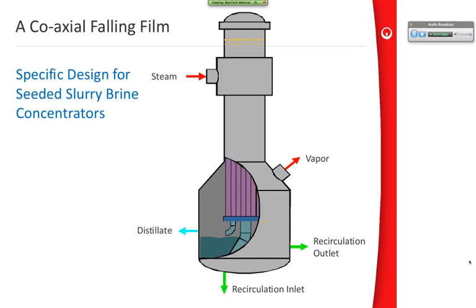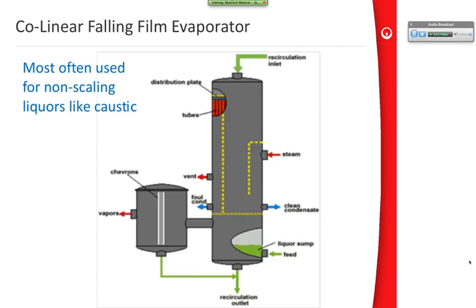The falling film evaporator is basically a heat exchanger that's welded onto a vapor body. The heat exchanger is up here at the top. It extends into the vapor body. The vapor body is a place in which the evaporated water vapor is separated from the brine. The brine collects in the bottom of this vapor body, which is sometimes also called a sump. It gets recirculated back to the top of the evaporator. Distillate is produced in the heating bundle, tube bundle, and the product is taken out.